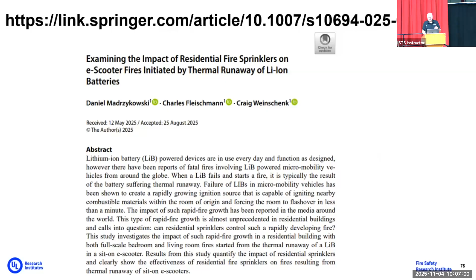There were components of the battery that we found on the sofas and on the carpet where they had started to burn into the cushion or the carpet, but then the sprinkler came on and wet those fuels and prevented them from participating further in the fire. So again, it prevented flashover and reduced the hazard in that structure. This study was recently published a few months ago, and you have full access to that.